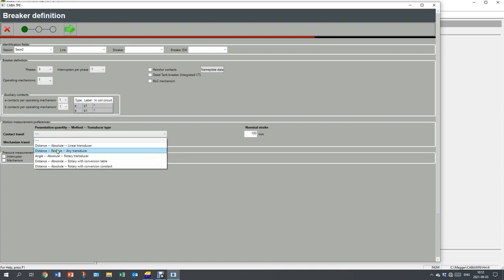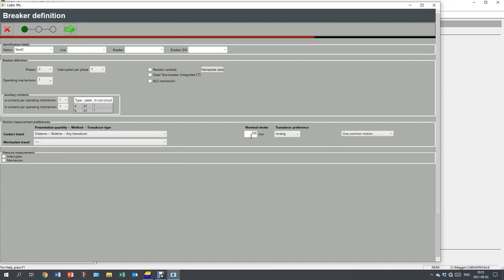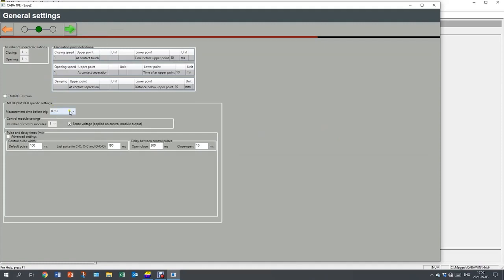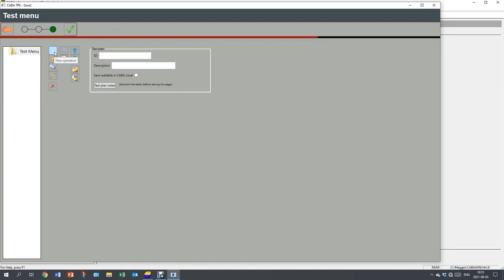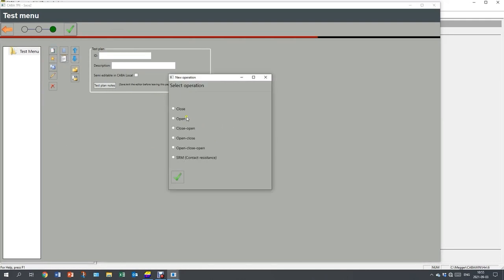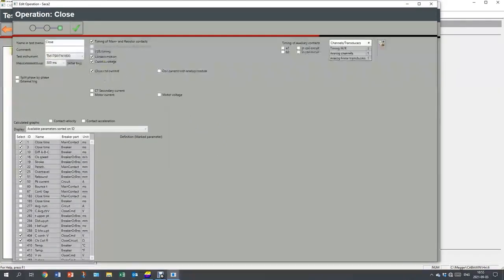I'm going to use relative, and I'm going to use 100 as nominal stroke, and it's one common motion. I want to have a pre-trigged measurement time, so I set this one to 100, and I continue and create my menu. I want to close operation, and I want to measure motion, voltage, and current. And my auxiliary contacts. And I'm going to use the control circuit to measure it. So it's in the coil circuit.